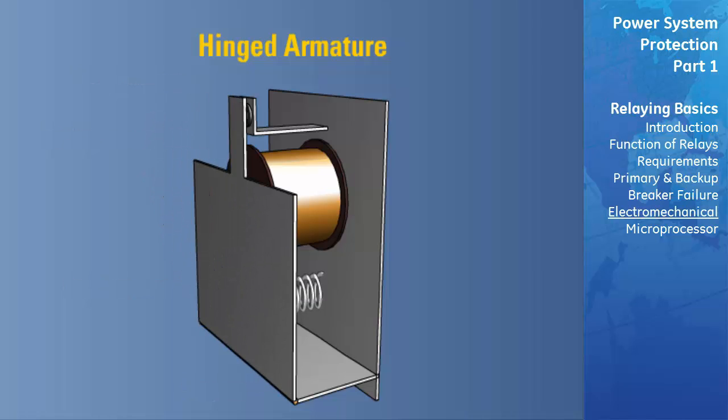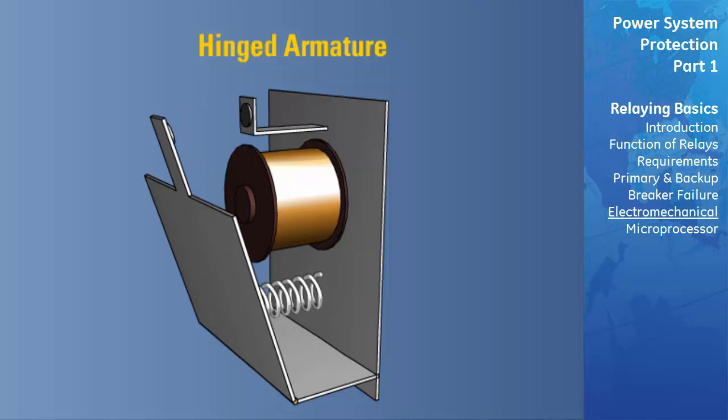As the hinged armature relays operate, the length of the magnetic air gap changes, resulting in a slightly greater force required to just pick up the armature than the amount of force that is required to release the armature. This translates into a difference in the amount of measured quantities for pick up and drop out, which is a slight impairment for this style of relay. This shortcoming also applies to the plunger style of construction, but to a lesser extent.